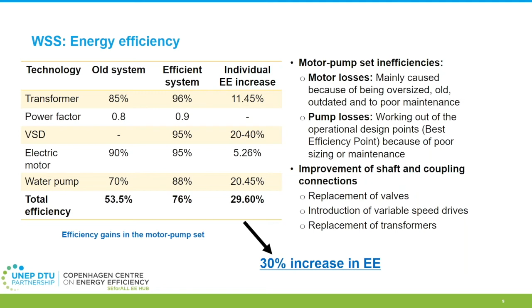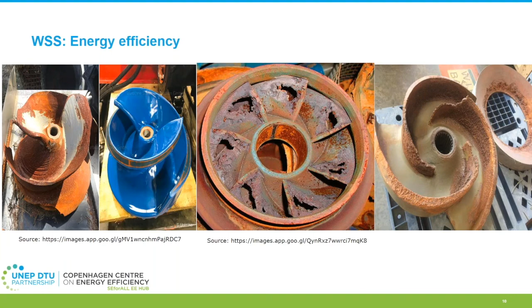This is from one of the field studies - I took a photo of this myself. If you look into this, it's not just technology-wise or efficiency-wise; at times you might have to open up old systems and look into the interiors. If you see here, there are corroded or almost damaged impellers of the pumps - the metal is literally eaten away. This causes disturbances and induces inefficiencies that creep into the system in many ways, eventually consuming a lot of energy.